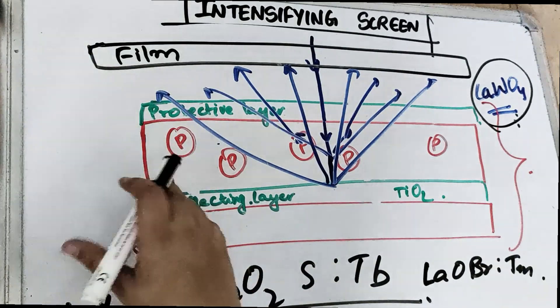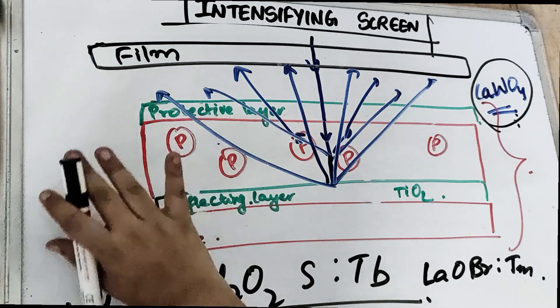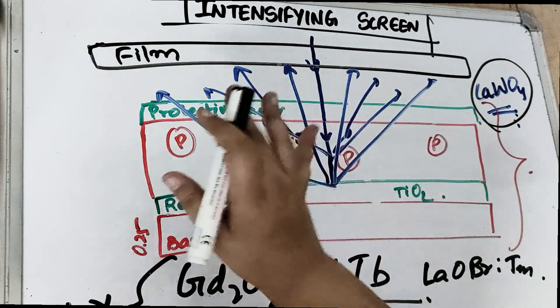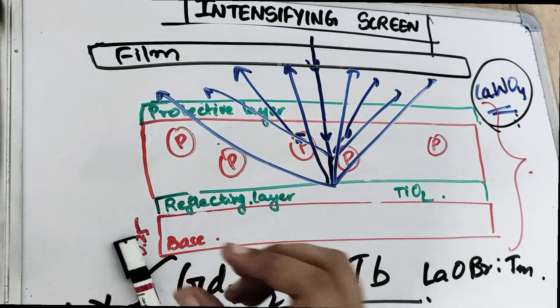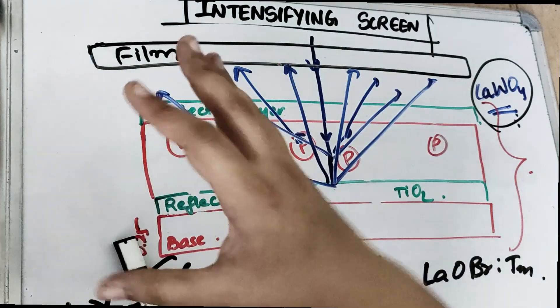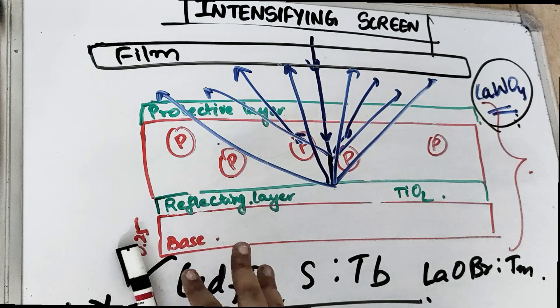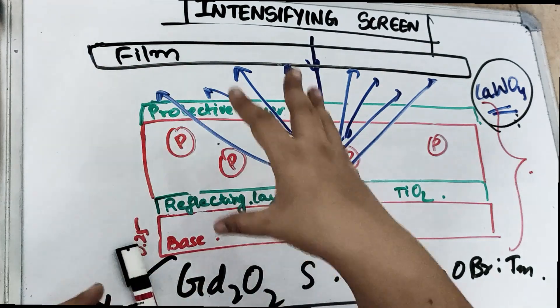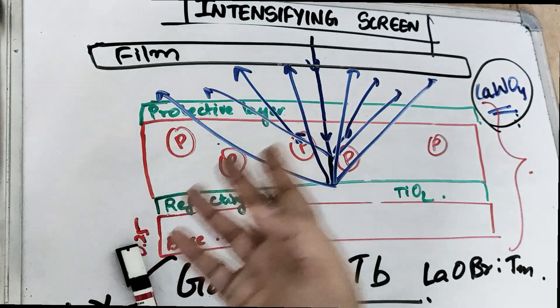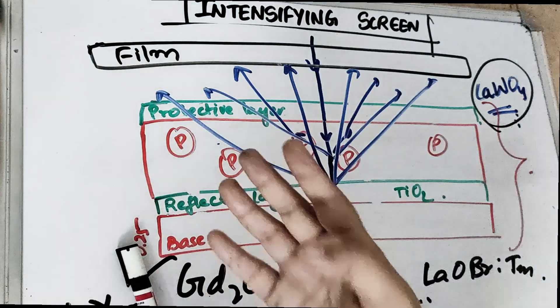So if the screen is dirty, there will be spots on the image. To protect it — I know you will say the protective layer is there, but it is not going to protect from dust, debris, or scratches. So we are going to keep it in a cassette. Like the old radio cassette had a box with a cassette inside, we have a cassette for the intensifying screen. But unlike the radio cassette which had one cassette per box, here in one cassette we have two intensifying screens — one on each side — so that exposure can occur on each side.